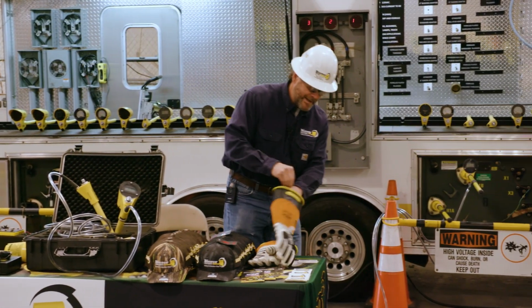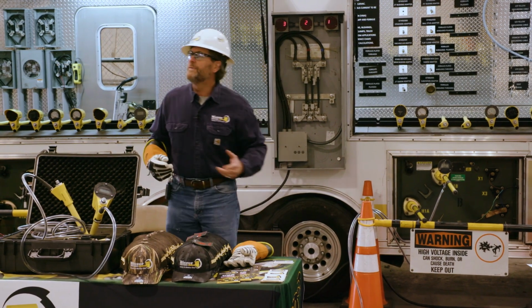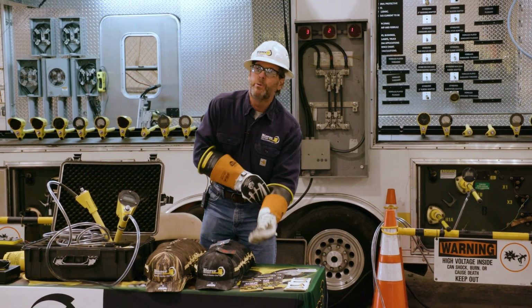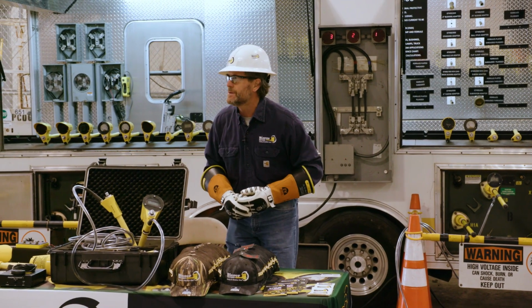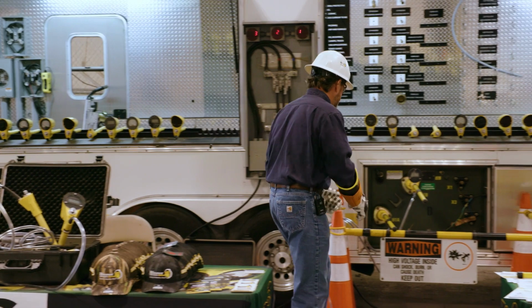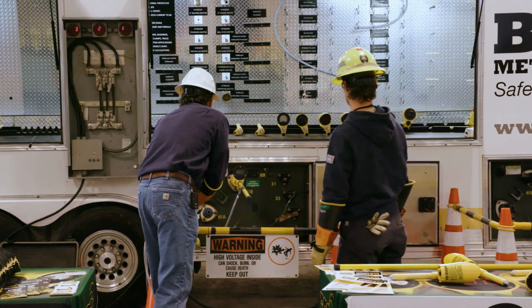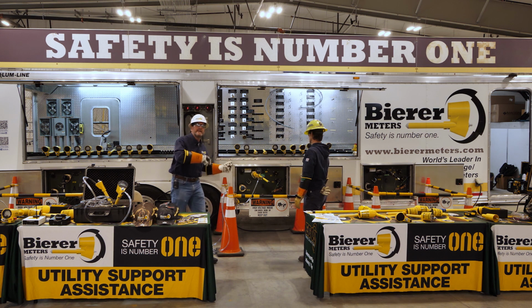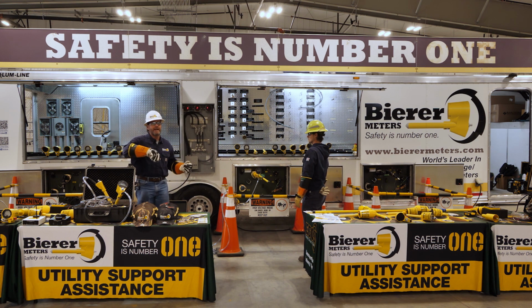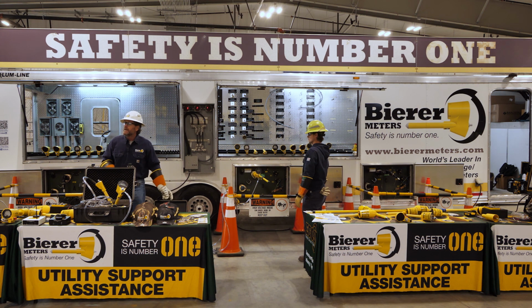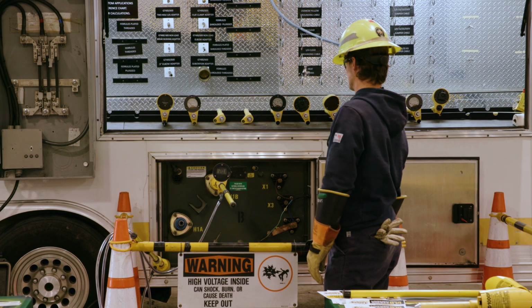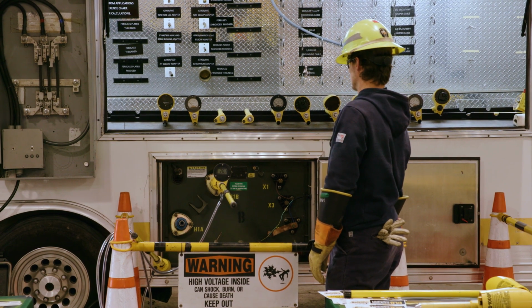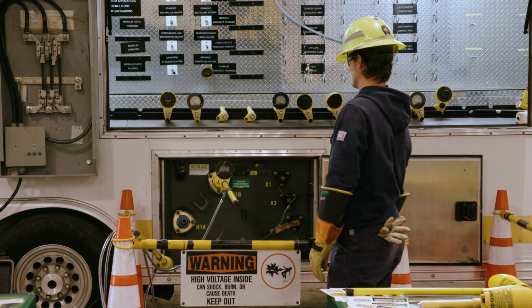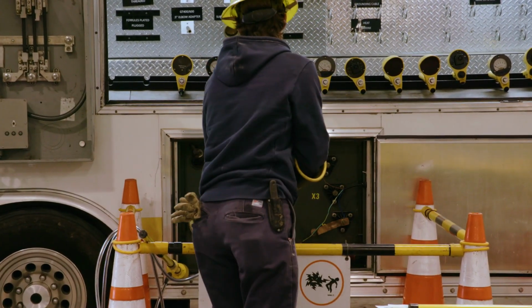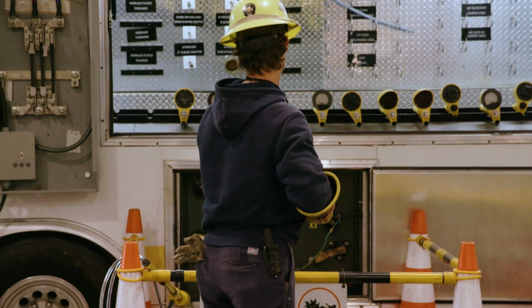All right. Now, if you're phasing or if you're high potting, you always want to pull the secondary probe and go to ground first. Always. And Mr. Robbie, when he disconnects and removes that off that hot bushing or that overhead line, he's going to see those numbers bleed off to 0, and he's going to recognize that it's going to take about 2 seconds. It's not instant. It takes about 2 seconds. All right, go ahead, Robbie. See what you see. Takes about 2 seconds.